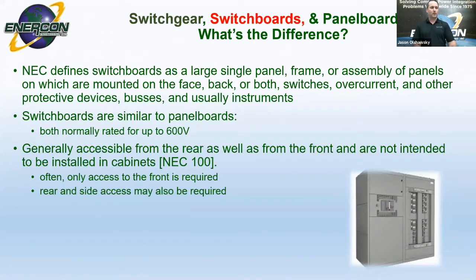All right. So the NEC defines switchboards as a large single panel frame or assembly of panels on which are mounted on the face, back, or both, switches, overcurrent, and other protective devices, buses, and usually instrumentation. Switchboards are similar to panel boards, both normally rated up to 600 volts, generally accessible from the rear as well as from the front, and are not intended to be installed in cabinets per NEC 100. Often only front access is required, and rear and side accesses may also be required.